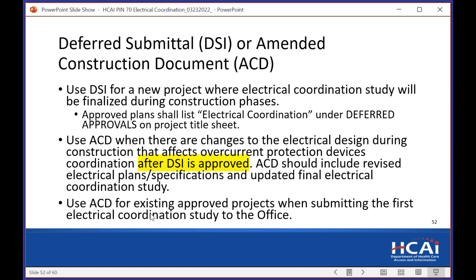Finally, for projects that are currently in construction and you never submitted a coordination study to the office, you don't use a DSI because we didn't require it during plan review, but we require your coordination study. Use an ACD to submit that to the office. Again, if you have changes based on the coordination study, you can submit those with the ACD that has the coordination study. Another option is if you did an ACD that changed all your single line diagrams and your panel schedule, and now you want to submit an ACD for the coordination study, you can do that as well. But we will be comparing your approved plans with the information provided in the coordination study.